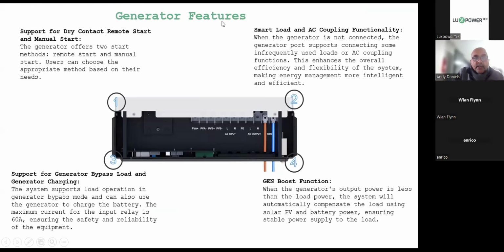functionality. All right, so underneath the machine here, the machine's been flipped over on its back, and this is what it looks like from the bottom. So here we have the gen port, and typically you will have your live and your neutral going in here from the generator. Now remember that your generator input, we discussed this previously, regardless of the size of the generator exceeding 6 kilowatts, the maximum power that the inverter will draw from it at any given time is 7.2 kilowatts. And that is to take the load and charge the batteries.